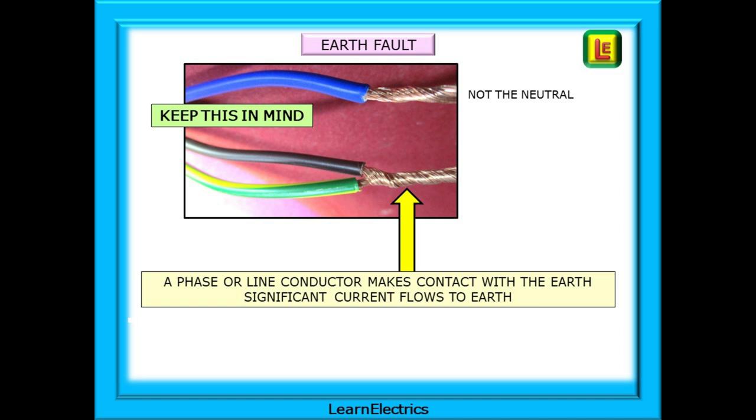A visual reminder of an earth fault that always worked for me when I was learning looked something like this. The line and CPC are connected together. It's telling me that somewhere in that circuit the line and earth or a phase and earth have found electrical continuity. It might be direct cable to cable contact. It might be through metal work but somewhere there is continuity and with earth faults we should expect significant current to flow hundreds of amps.